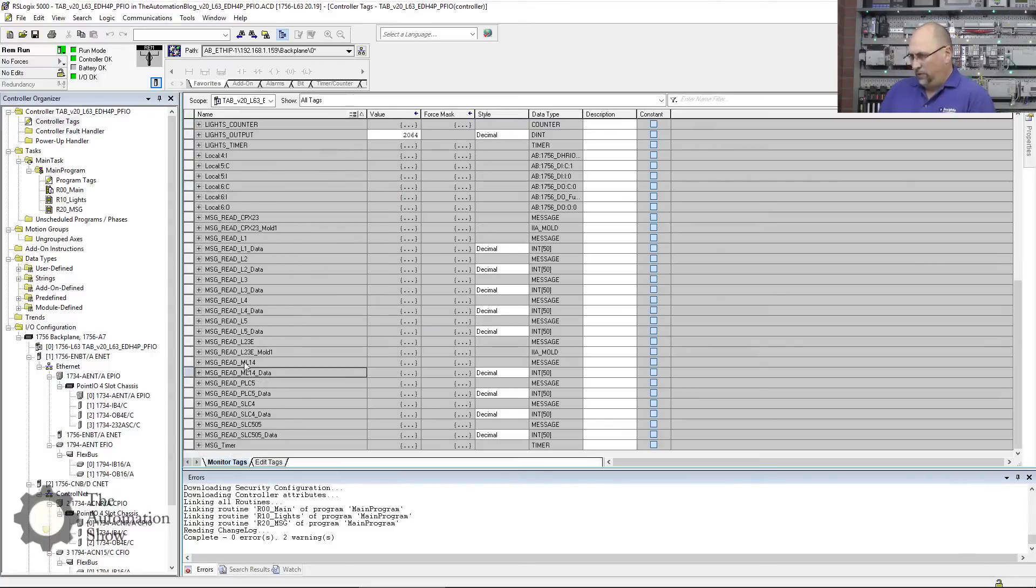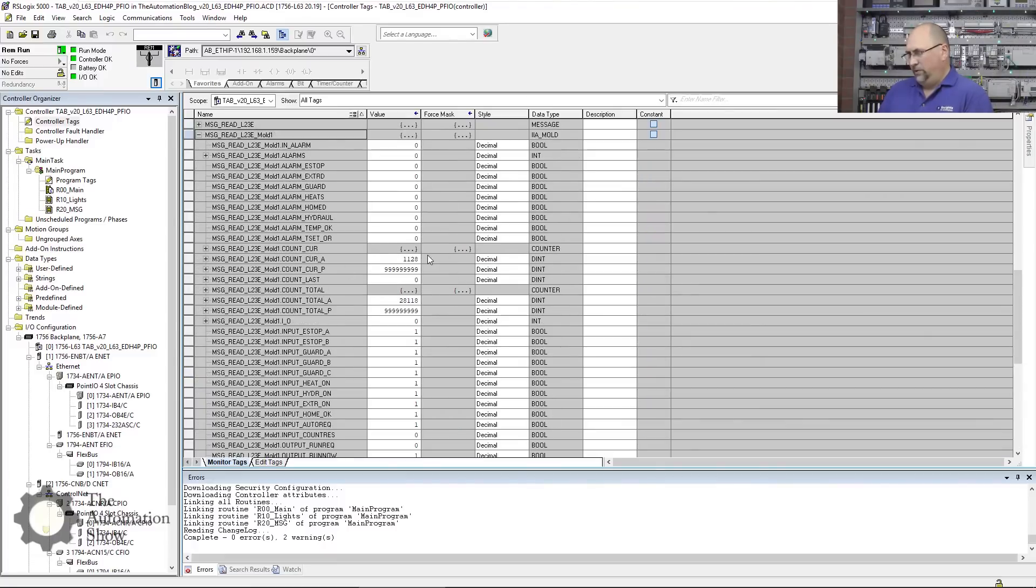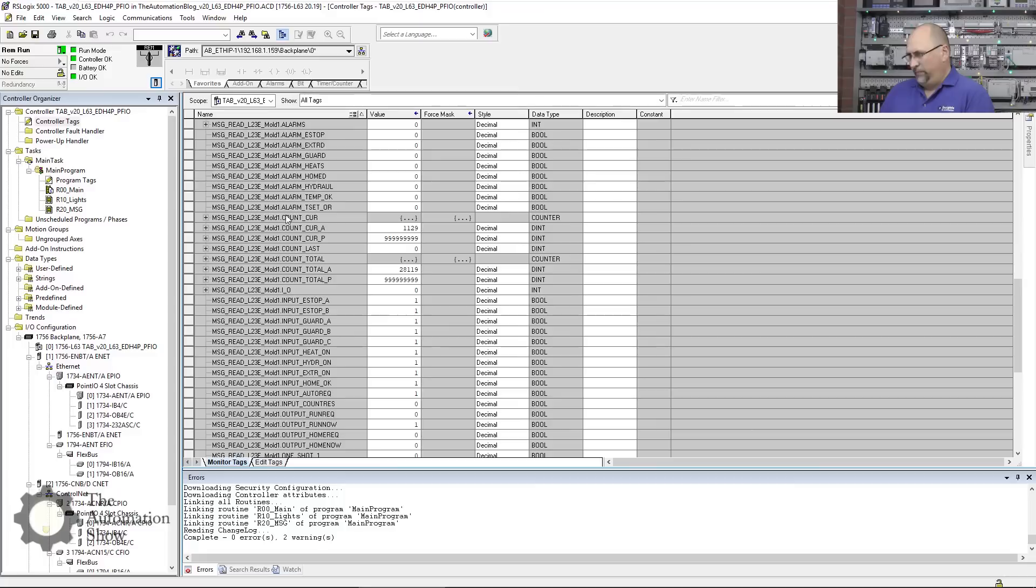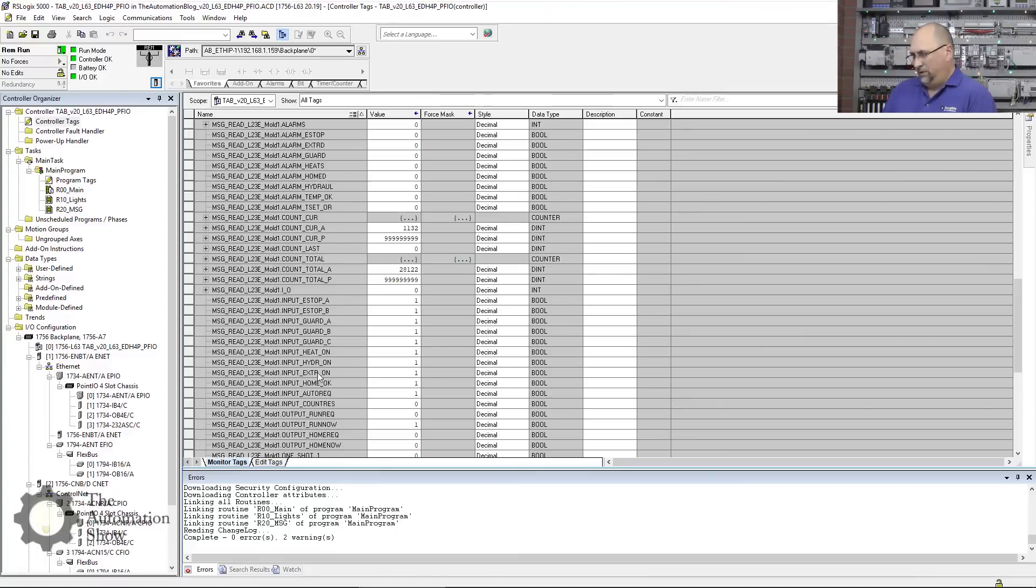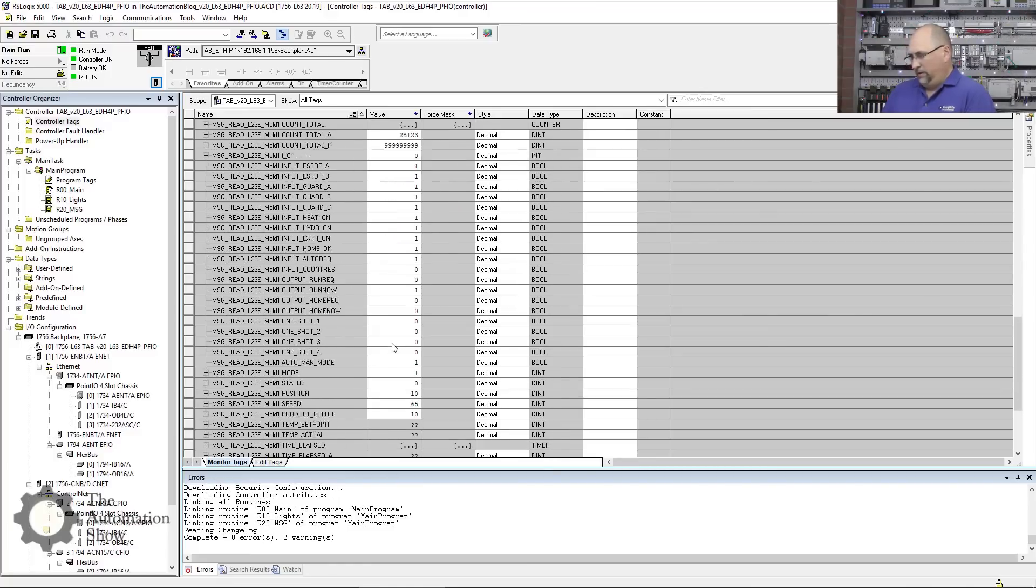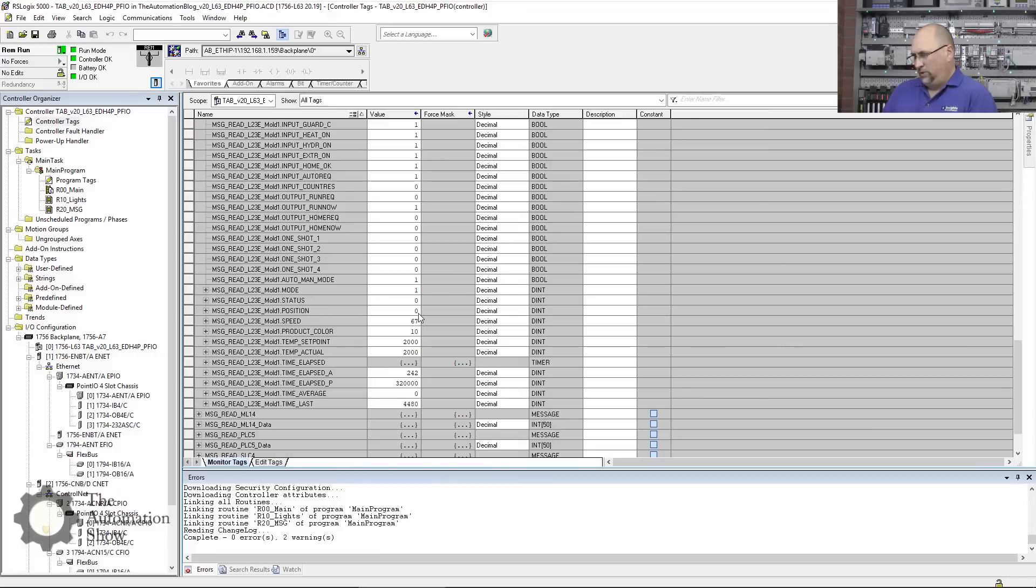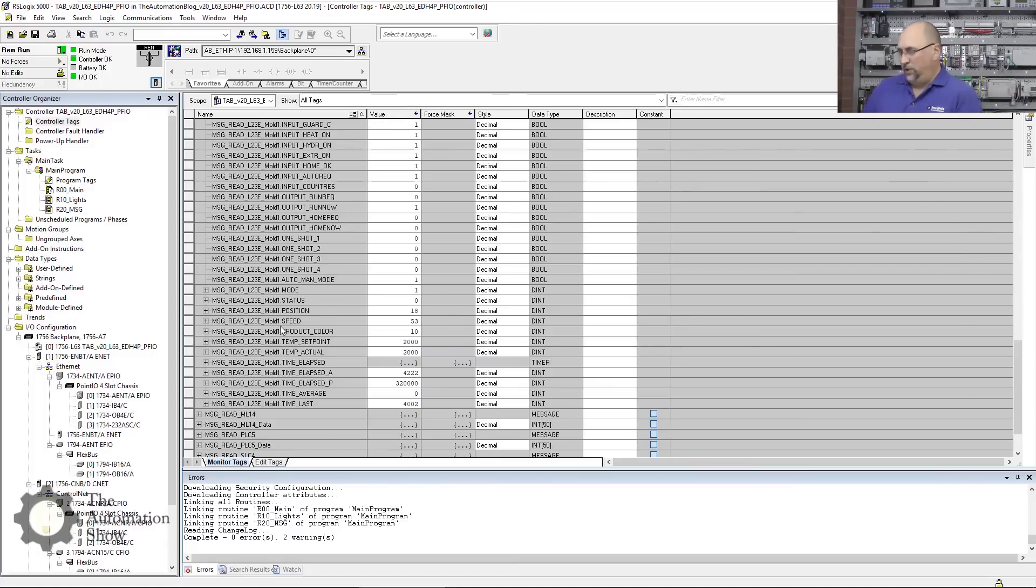Last but not least, we want to look at the L23E, and that was Mold_One, so I'm only going to get one mold out of that. We got a lot of bits in here. Current count—yep, we just saw that change every two seconds. Yep. We see another total accumulator value. Nice thing about this is it's all defined for us, so we know what each one of these values is. We see anything else here? What do we got down here? Molding speed, product color. You can see the speed is changing, positions changing, elapsed time here. Making parts pretty quick over there on the blow molding machine, so they change pretty fast.